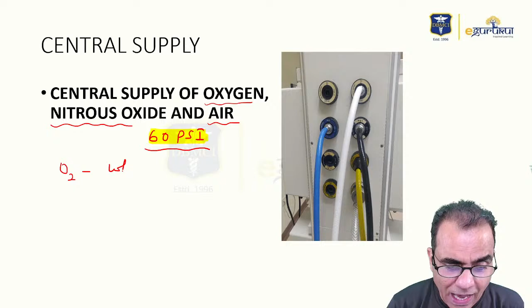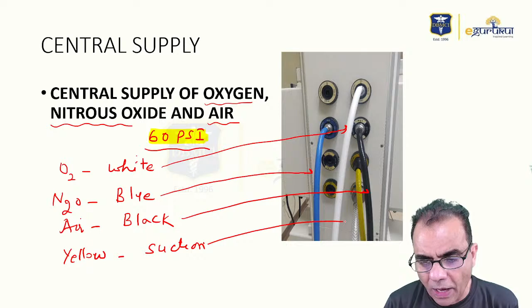And there is color coding for the pipes also. Oxygen will be carried by white color pipes, nitrous oxide by blue color pipes, air by black pipes. Then there is a fourth pipe that you will see, yellow, and that yellow pipe is for central suction or vacuum. So this white pipe, obviously, is for oxygen. This blue pipe is for nitrous oxide. This black pipe obviously is for air, and this yellow pipe is for vacuum, central suction.